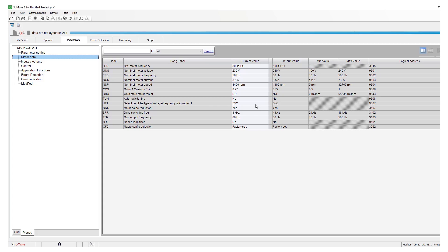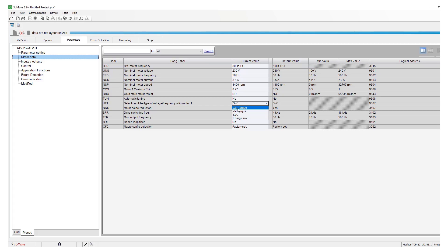Make sure it's set per application. For example, if it is a fan application, make sure it's set for variable torque. If it is a constant torque application, you can either select constant torque or SVC. Another thing to check is the ITH.